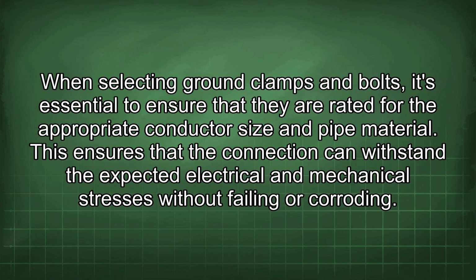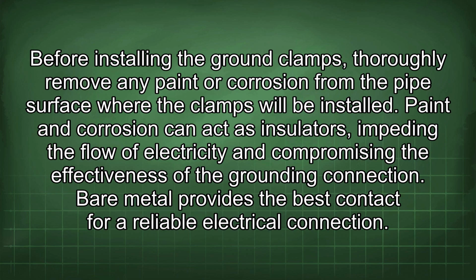When selecting ground clamps and bolts, it's essential to ensure that they are rated for the appropriate conductor size and pipe material. This ensures that the connection can withstand the expected electrical and mechanical stresses without failing or corroding. Before installing the ground clamps, thoroughly remove any paint or corrosion from the pipe surface where the clamps will be installed. Paint and corrosion can act as insulators, impeding the flow of electricity and compromising the effectiveness of the grounding connection. Bare metal provides the best contact for a reliable electrical connection.